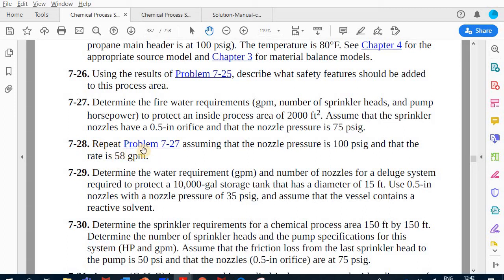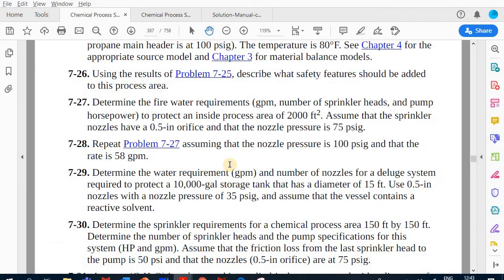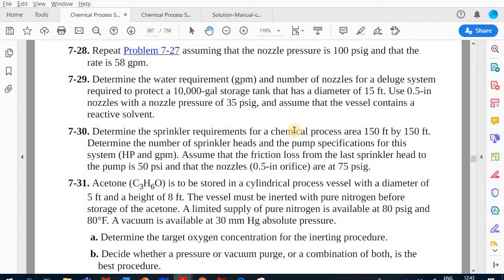Problem 7-28 is essentially the same approach but with different values: 100 psi gauge and 58 gal/min per nozzle. Even without being told the orifice size, you can look up 100 psi gauge in Table 7-7 to find 58 gal/min and identify the nozzle from there.